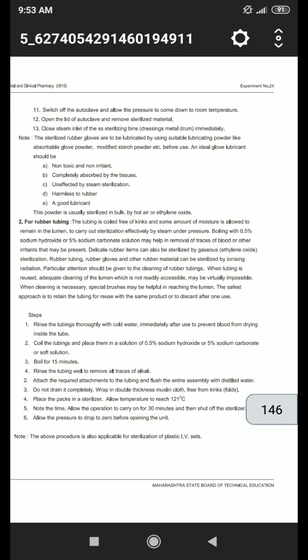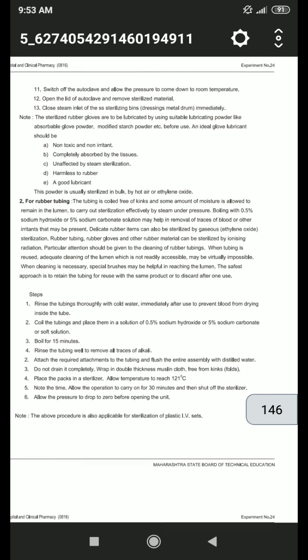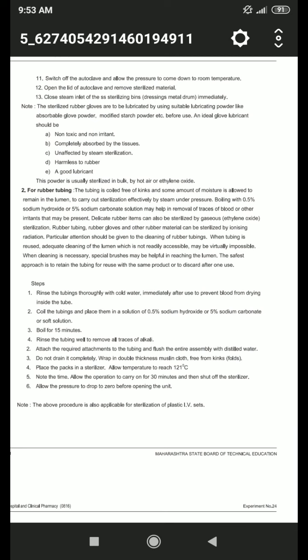Then rinse the tubing well to remove all traces of alkali. Then attach the required attachment to the tubing and flush the entire assembly with distilled water. Do not drain it completely. Then wrap in double thickness muslin cloth, free from kinks, that is, folds. Then place the packs in the sterilizer and allow the temperature to reach 121 degrees Celsius. Note the time, allow the operation to carry on for 30 minutes, and then shut off the sterilizer. Then allow the pressure to drop to 0 before opening the unit. Okay, these are the steps for rubber tubing.